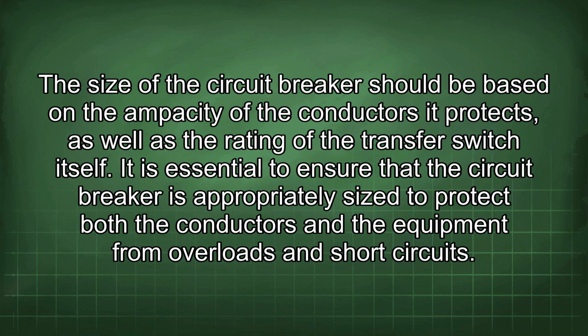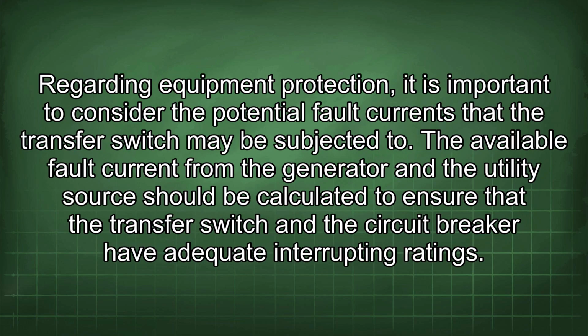The size of the circuit breaker should be based on the ampacity of the conductors it protects, as well as the rating of the transfer switch itself. It is essential to ensure that the circuit breaker is appropriately sized to protect both the conductors and the equipment from overloads and short circuits. Regarding equipment protection, it is important to consider the potential fault currents that the transfer switch may be subjected to. The available fault current from the generator and the utility source should be calculated to ensure that the transfer switch and the circuit breaker have adequate interrupting ratings.